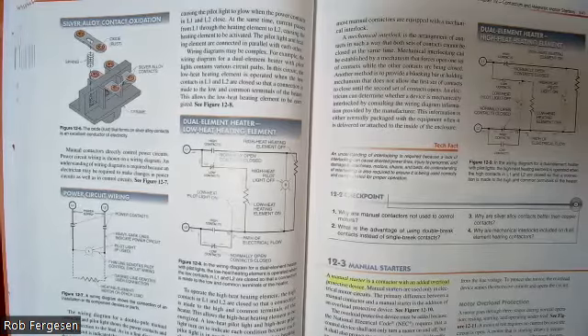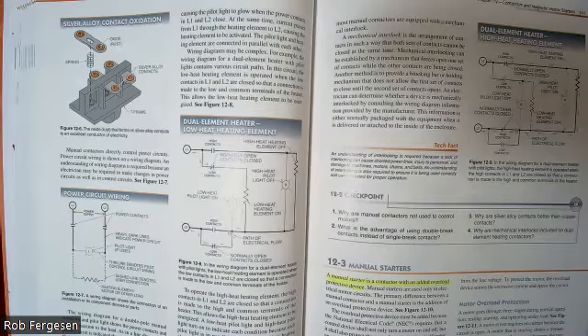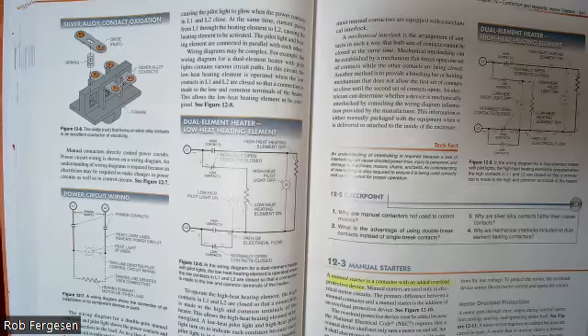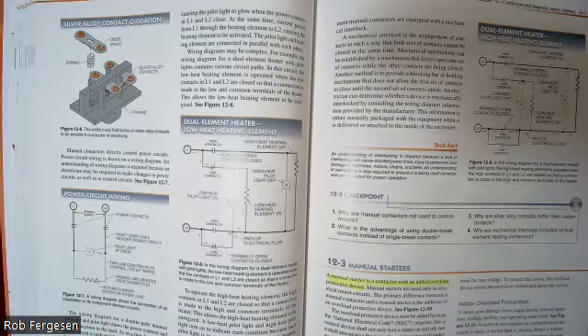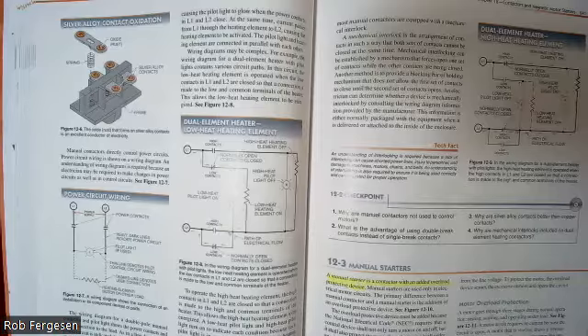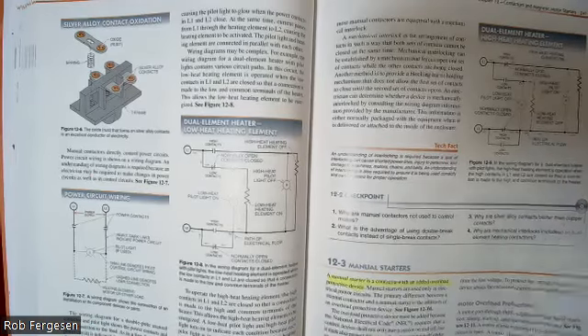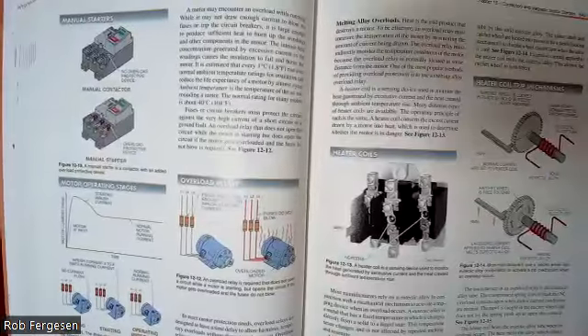A manual starter. The difference between a starter and a contactor is motor protection. That should be the number one thing you understand right now. By putting that motor overload protection in the circuit, you convert that switch or that contactor into a starter. A starter allows you to have a higher initial current while the motor is starting up, but if the motor runs long enough at too high a current, it will blow the circuit protection one way or another. So let's talk about how it's going to do that.